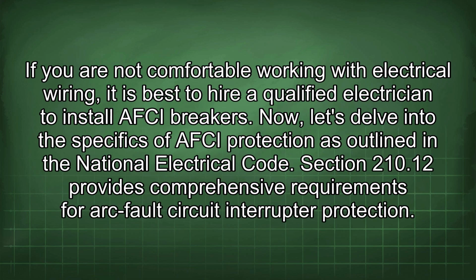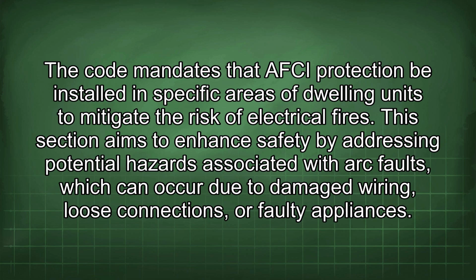If you are not comfortable working with electrical wiring, it is best to hire a qualified electrician to install AFCI breakers. Now, let's delve into the specifics of AFCI protection as outlined in the National Electrical Code. Section 210.12 provides comprehensive requirements for arc fault circuit interrupter protection. The code mandates that AFCI protection be installed in specific areas of dwelling units to mitigate the risk of electrical fires. This section aims to enhance safety by addressing potential hazards associated with arc faults, which can occur due to damaged wiring, loose connections, or faulty appliances.